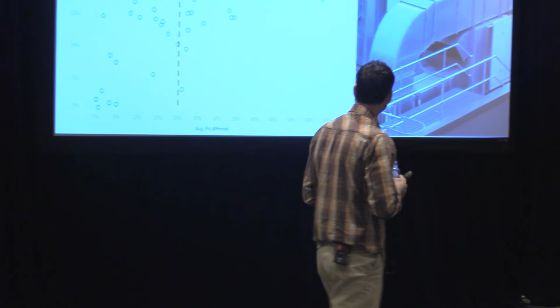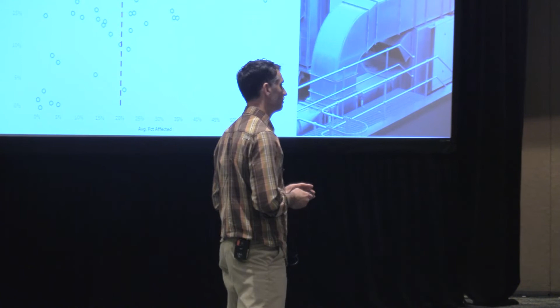I think that may be one of those where you're plugging into the sequences, and it may be related to a reset schedule where a certain set point is expected, but it's not actually happening. So maybe there's a conflict in the controls there, or some data issue that's causing a conflict there. I can't be more specific without seeing the list of all the raw faults that feed into that, but it kind of implies that you need to really look at the programming and set points to work out what is actually in conflict there. It's supposed to be some set point, but it's not. Sorry. I was saying I can understand that in a common thing where it's supposed to bring that a set point, but there's a switch off in the programming and stuff.